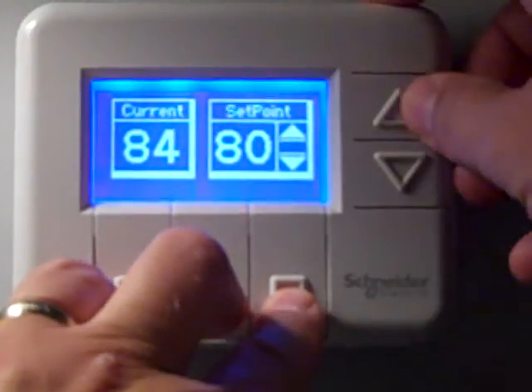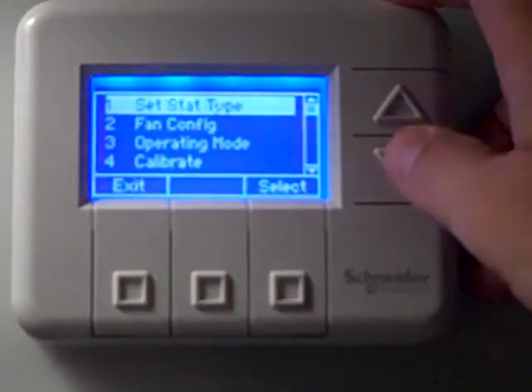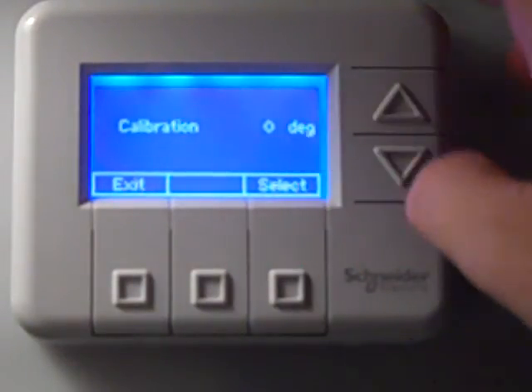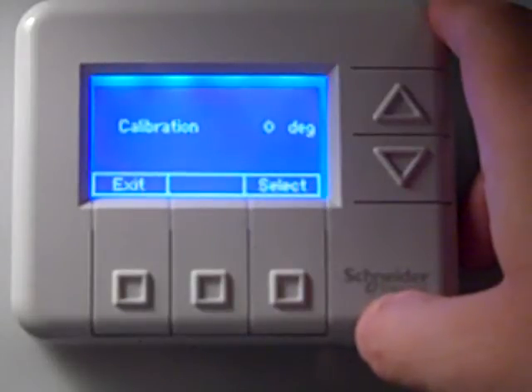Go into the thermostat main menu, go to Set Stat Type, press select, then come down to number four — calibrate — and press select. There will be a value in there; that value could be zero, minus two, plus two, or another number.